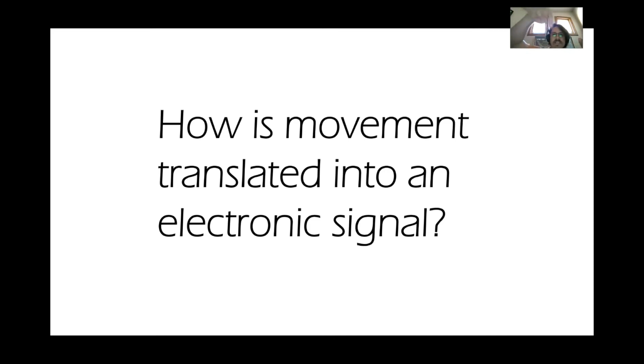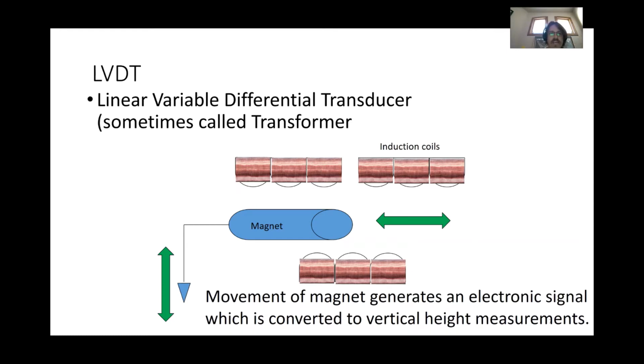Well, you have this needle riding, okay, so you have a whole gantry where this needle is riding, and that's done with a linear variable differential transducer. Sometimes it's called a transformer. I'm missing the end of my parentheses there, I'm sorry. But the movement, so the stylus moves, which then moves the magnet, and I have a weird, kind of vertical to horizontal translation in my depiction.